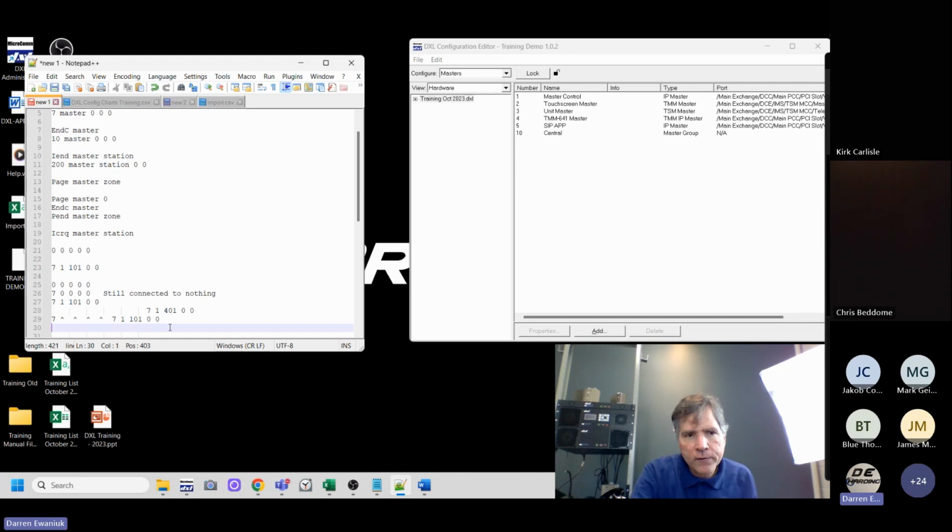So that's just something to note. Our system operates when the first register is written. If you write it as a block, which is going to happen in almost all cases, then you don't have a problem. You just do things logically, do things normally, and things will work. But if, for whatever reason, your PLC or your data acquisition server or whatever driver you're using does it only one at a time, then make sure you write the first register last. The order doesn't matter for the rest of them.